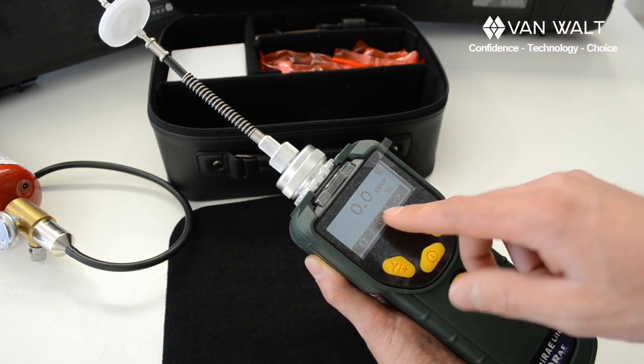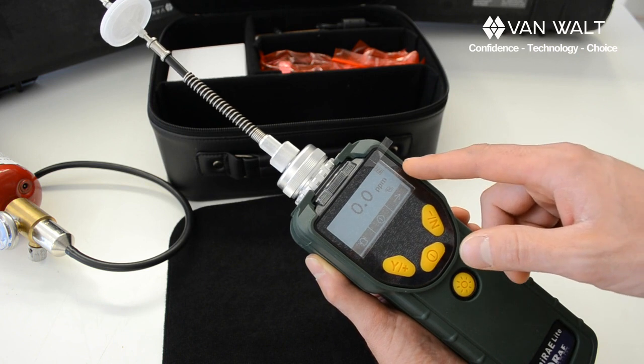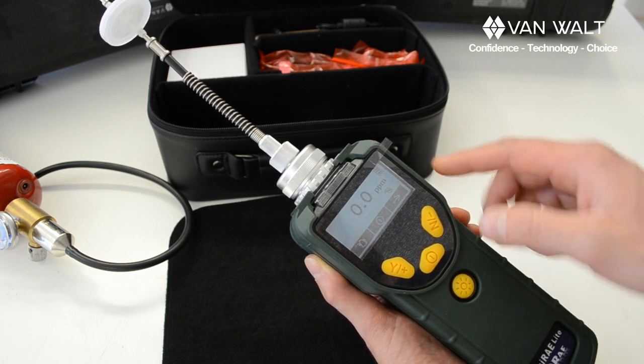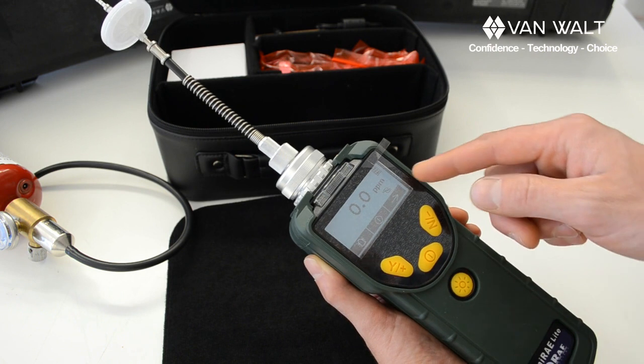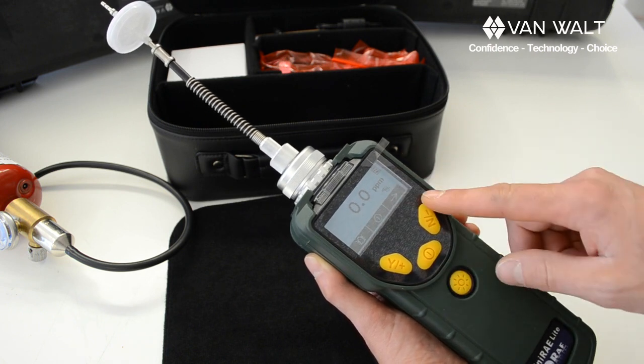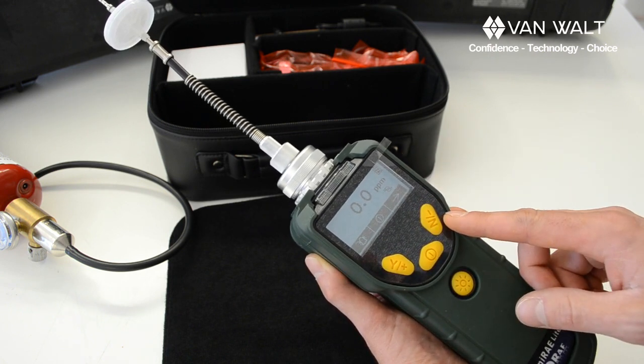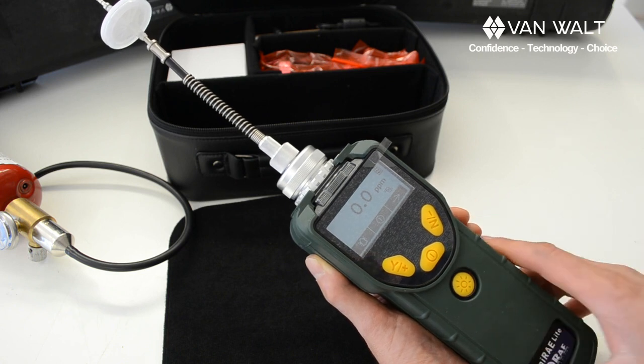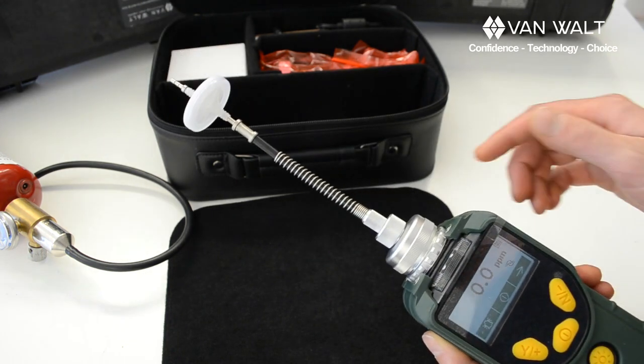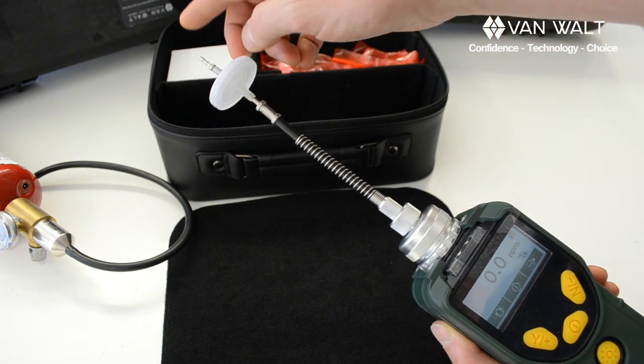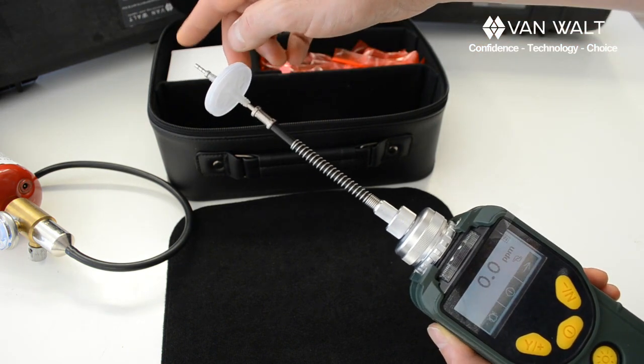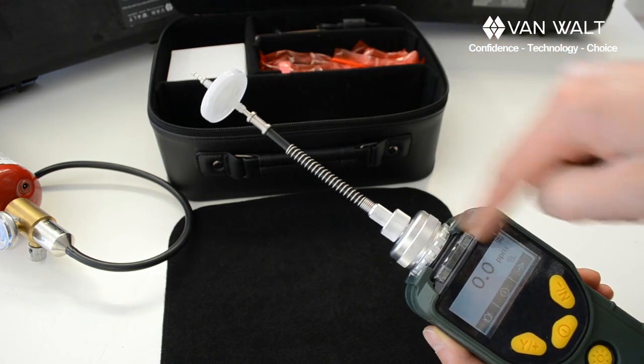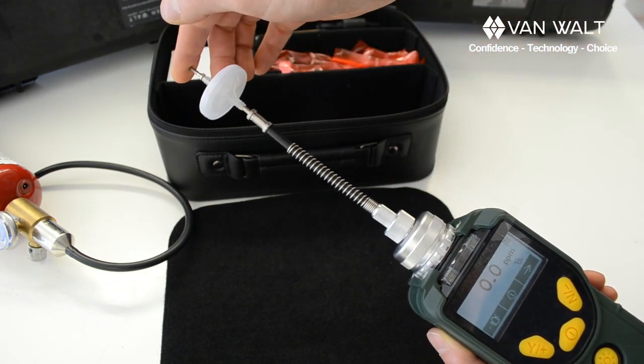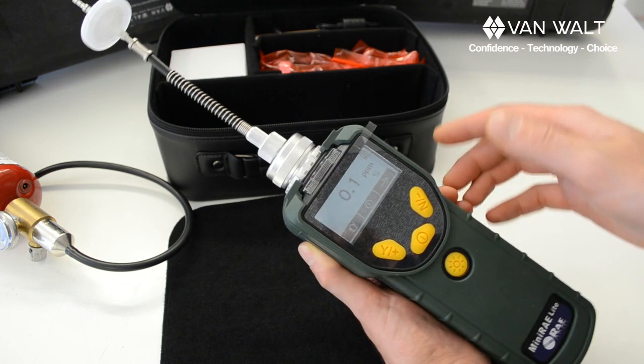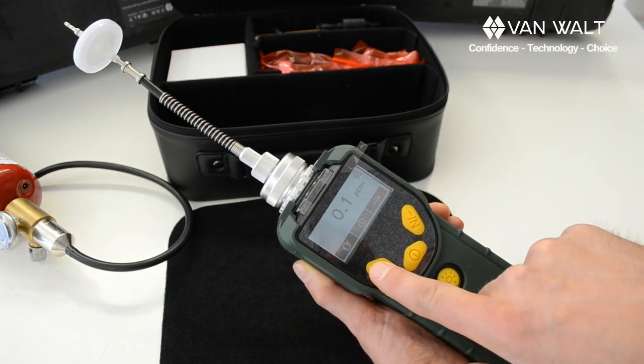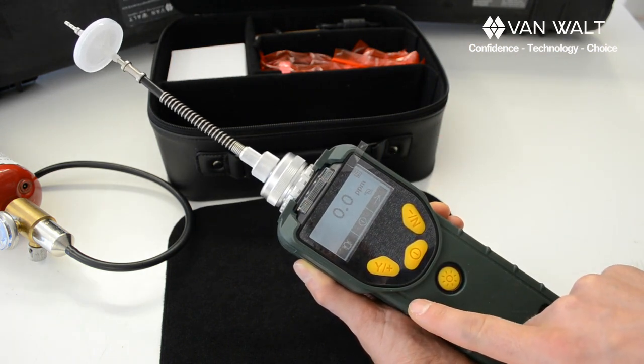So we're looking at the moment, we're in a fairly fresh air environment. It's reading 0.0 parts per million, so that's our first initial bump test, to look at that in our clean environment. What we can do also is, this is a good time to do a stall test, so I'm going to put my finger over the top of the nozzle, and hopefully the machine will stall to prove that there are no air leaks in the system. Yep, so it's complaining, and we'll shut that off with the left hand button there.